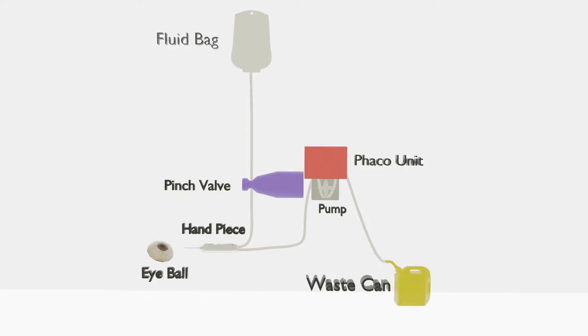Let's look into components of a PHACO machine. The major components of the PHACO machines are fluid bag, pinch valve, peristaltic pump, handpiece, foot switch, and waste can.